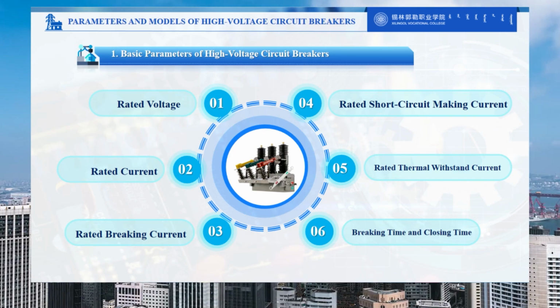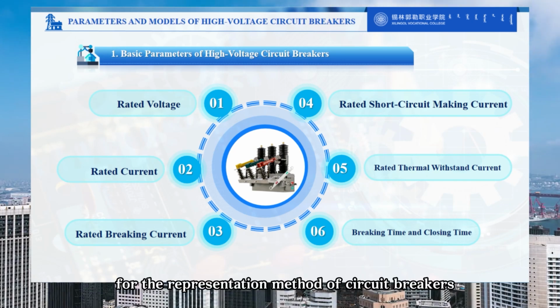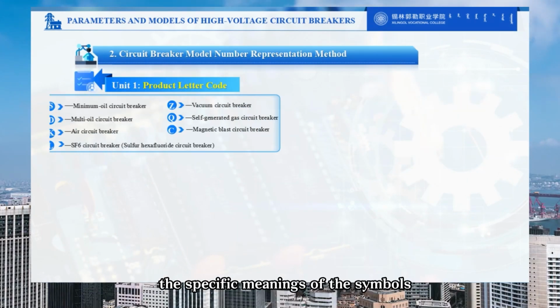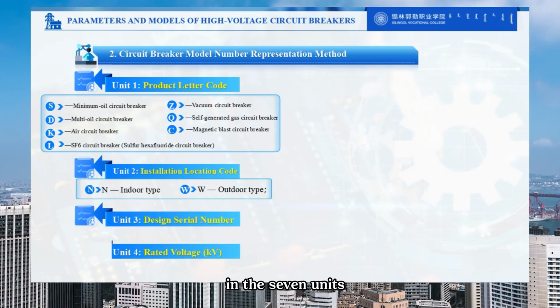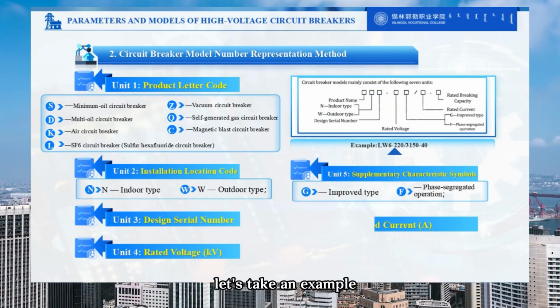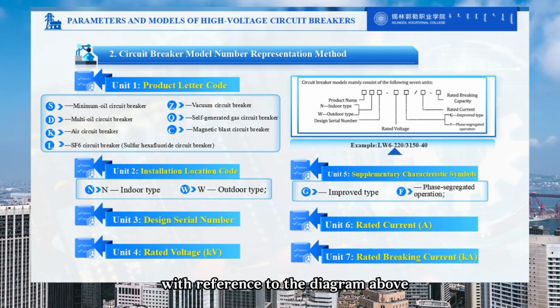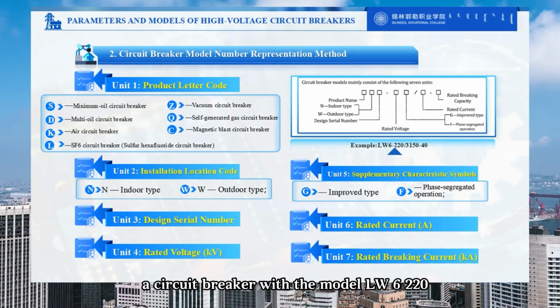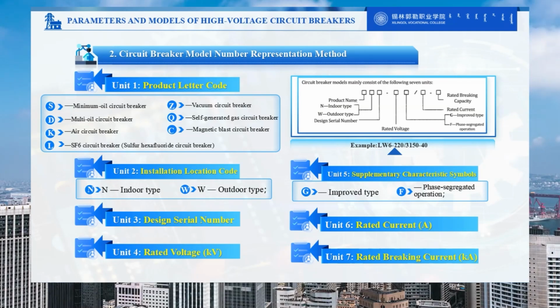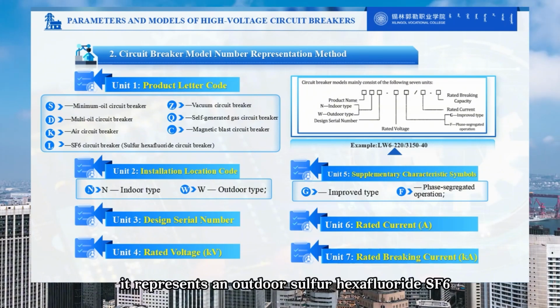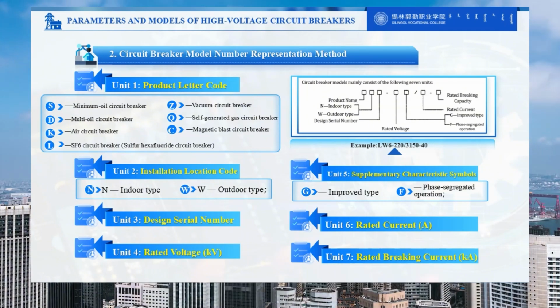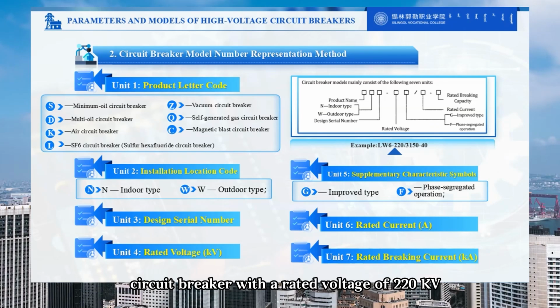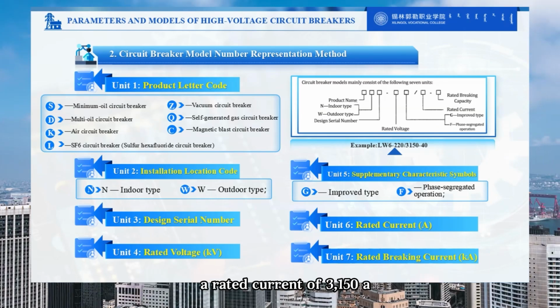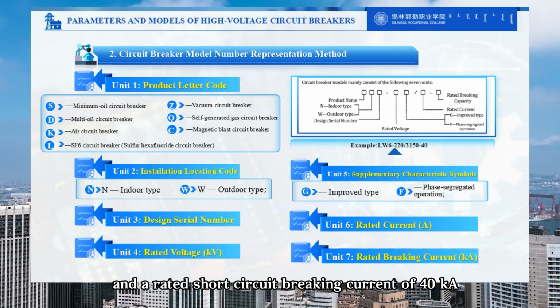For the representation method of circuit breakers, we only need to remember the specific meanings of the symbols in the 7 units according to the schematic diagram. Let's take an example with reference to the diagram above. A circuit breaker with the model LW6-220/3150-40 represents an outdoor sulfur hexafluoride SF6 circuit breaker with a rated voltage of 220 kV, a rated current of 3150 A, and a rated short-circuit breaking current of 40 kA.